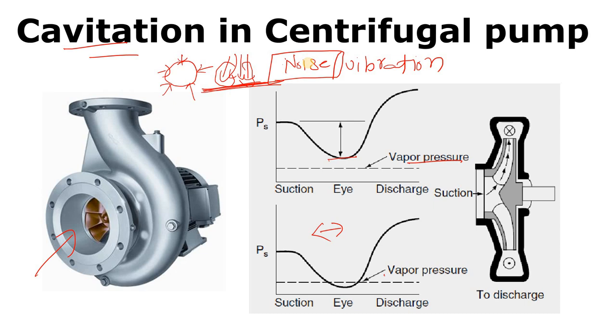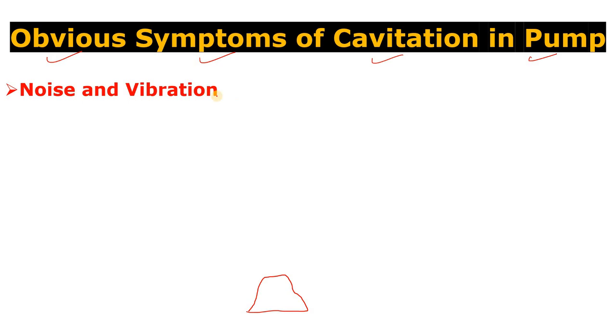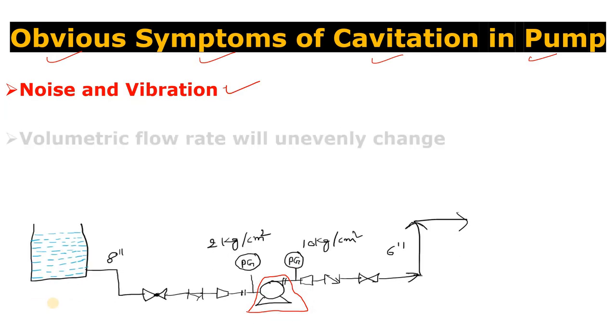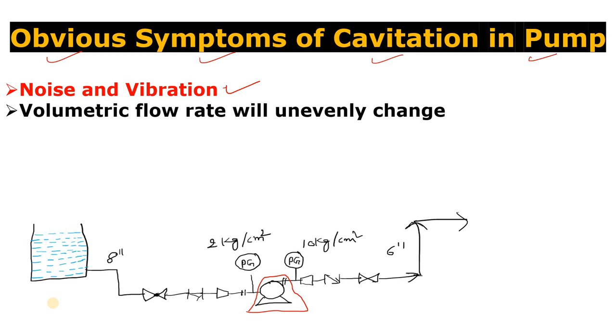So if you see noise and vibration from the centrifugal pump, you have to check the other parameters as well — the other symptoms. The second symptom is that the volumetric flow rate will unevenly change.